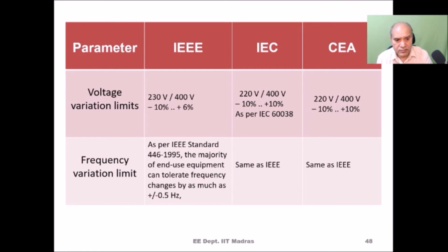I will give you just a brief idea of what it means to follow the standards. Mostly voltage and frequency are the first two important parameters that have to be followed within certain limits. For example, if you see IEEE, then IEC, then CEA, they are in close match. In fact, they are almost the same. Like voltage allowed is basically minus 10% downside and plus 6%, while IEC says minus 10 to plus 10%, and CEA says minus 10 to plus 10. This is the Central Electricity Authority of India. And frequency variations are normally plus minus 0.5 Hertz.